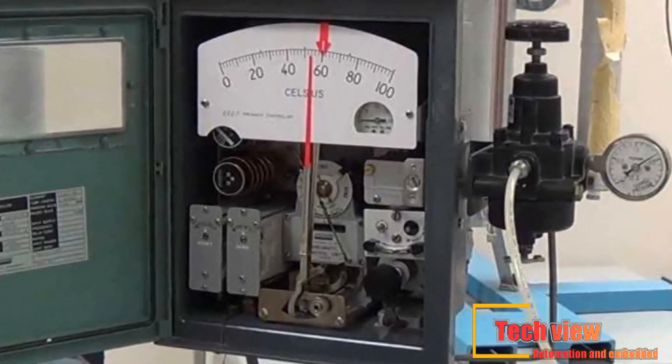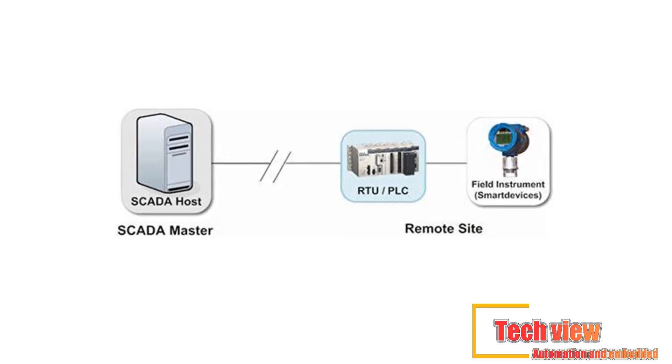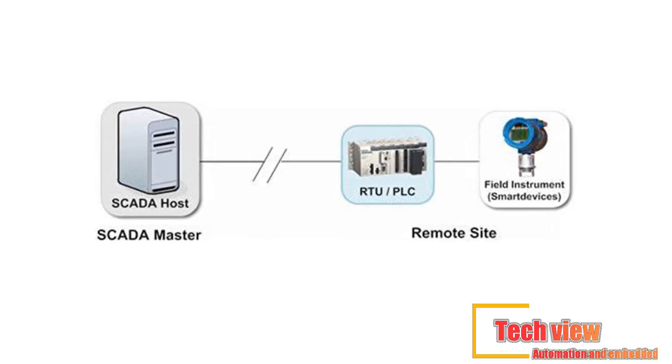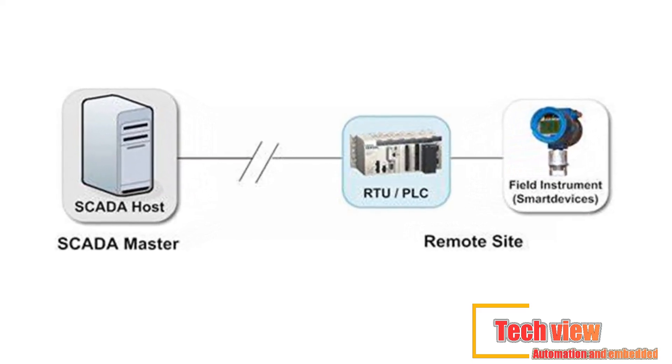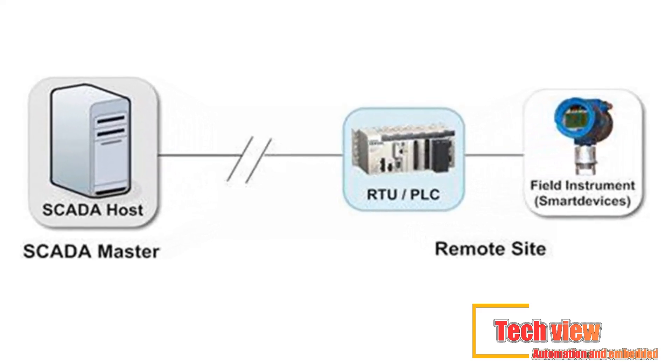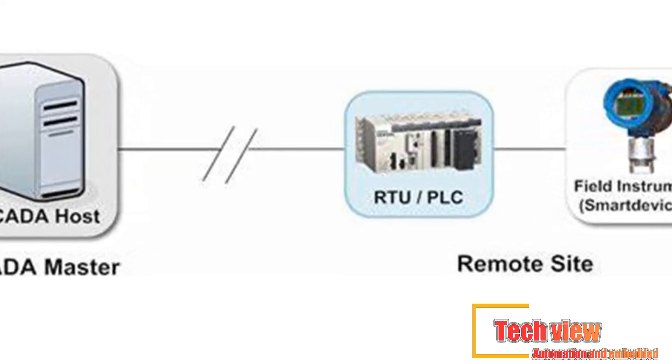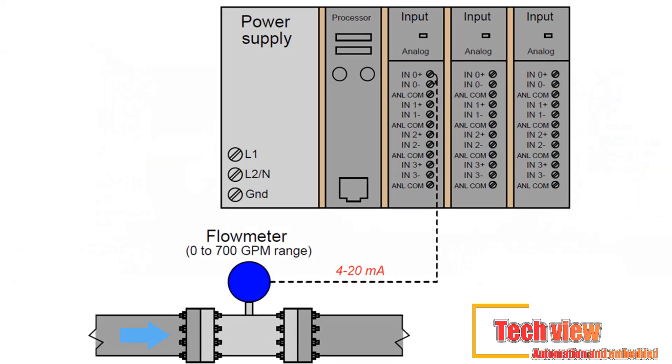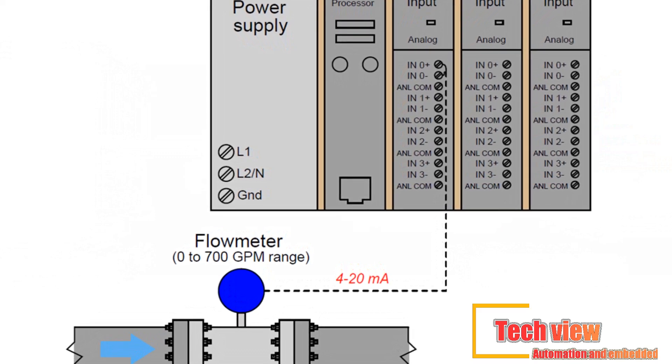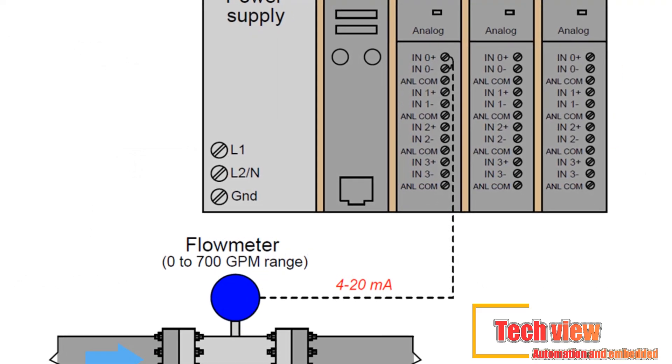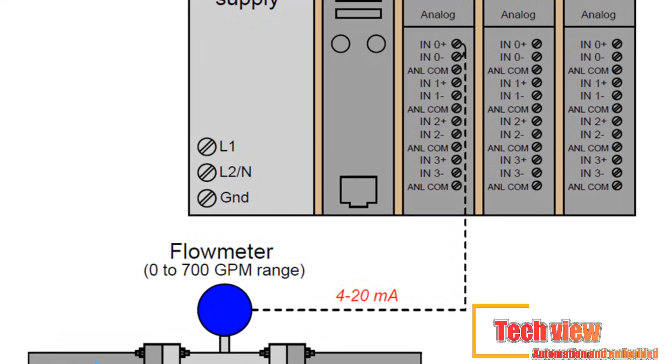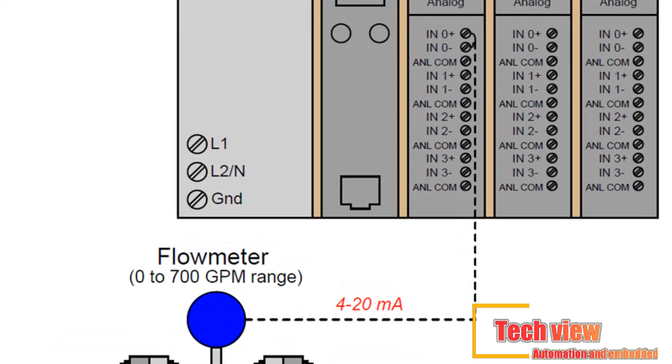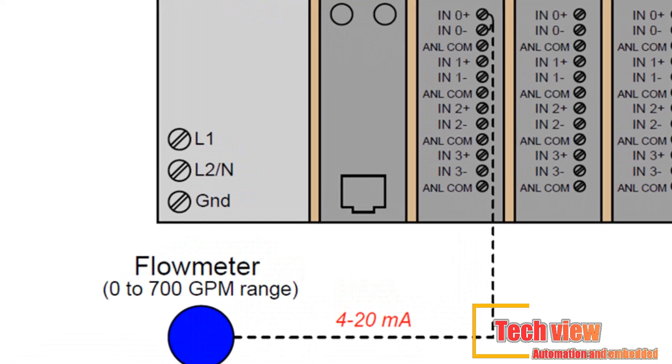Thus, instead of being wired directly to each other, all equipment is wired to the PLC. Then, the control program inside the PLC provides the wiring connection between the devices. The control program is the computer program stored in the PLC's memory that tells the PLC what's supposed to be going on in the system. The use of a PLC to provide the wiring connections between system devices is called soft wiring.